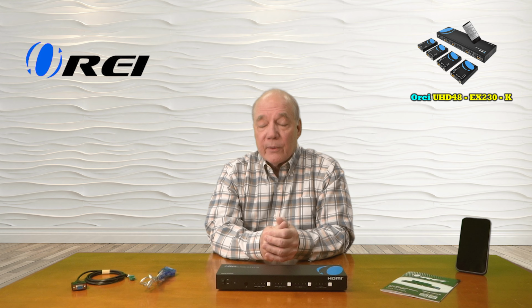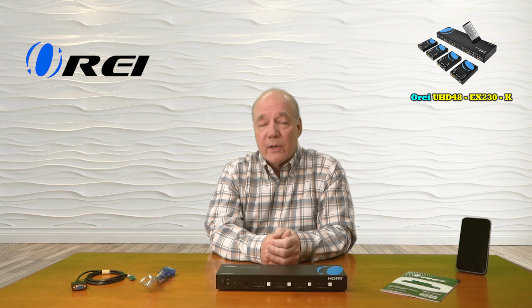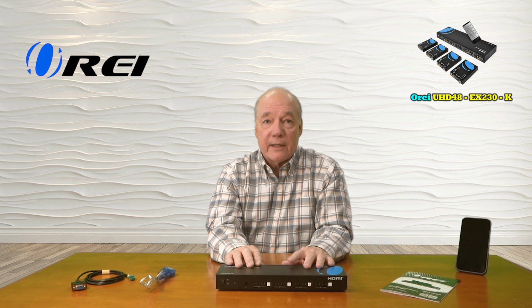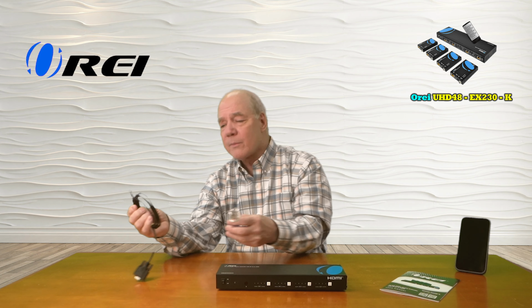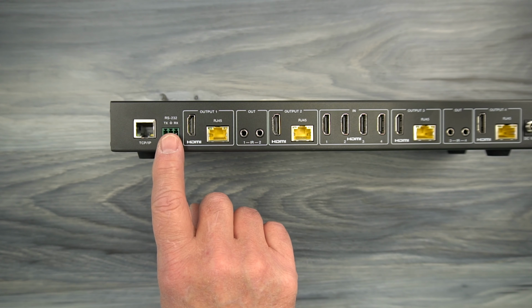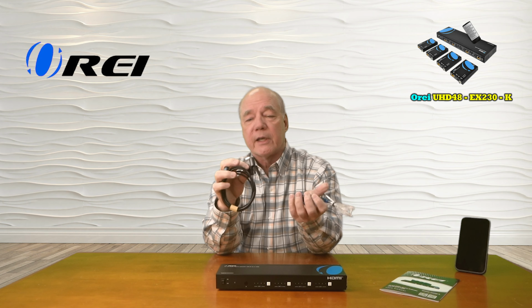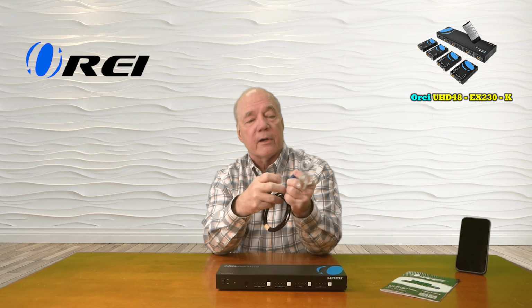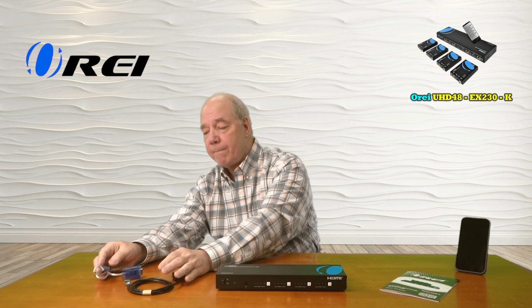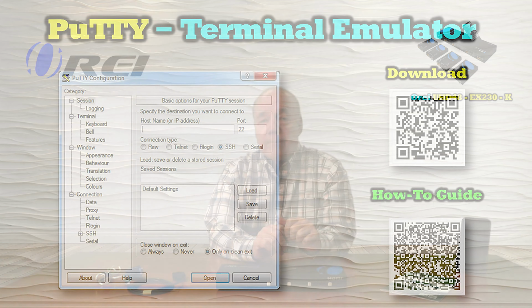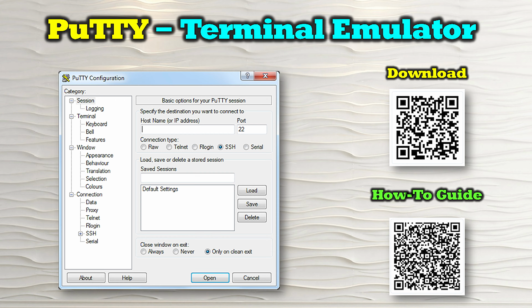The third way you can do it is through the RS-232 connection on the rear of the unit. Now, any product that's network connected comes with an RS-232 connection kit, which you can plug into the back RS-232 port. Then there's a connector here that plugs into this connector that terminates in a USB-A connection right here. So essentially, you'll plug this into your computer. You'll need to use a terminal emulator program. The easiest one to find is PuTTY.